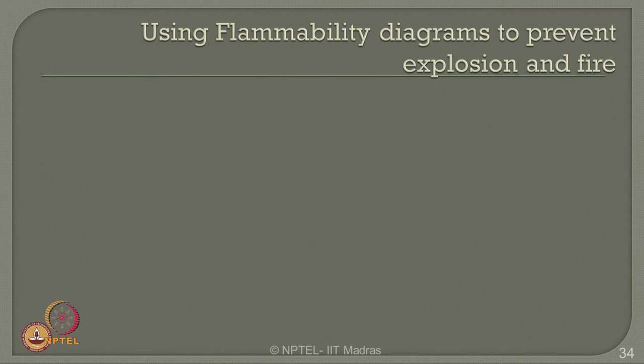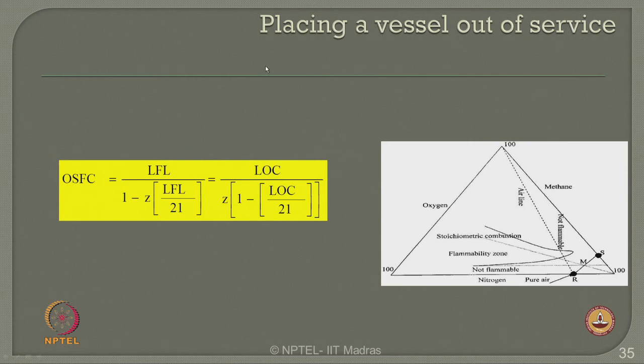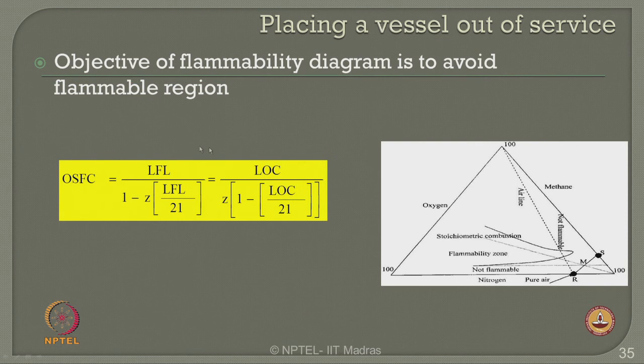One can also use flammability diagrams to prevent explosion and fire. The objective is to avoid the flammable region. The flammability diagram determines whether a flammable mixture exists and provides target concentration for inerting and purging. One can also use a technique called placing a vessel out of service. The flammability diagram has three arms: nitrogen, fuel, and oxygen, with values varying from 0 to 100 in an anti-clockwise manner. The diagram shown is for methane as the fuel, and the flammable region is plotted depending on the LOC, LFL, and UFL of the fuel arm.